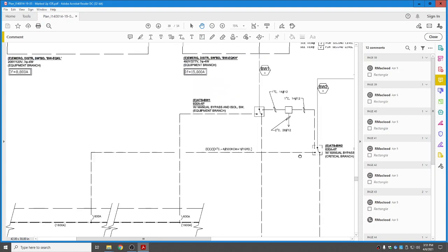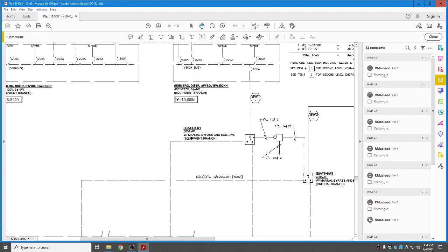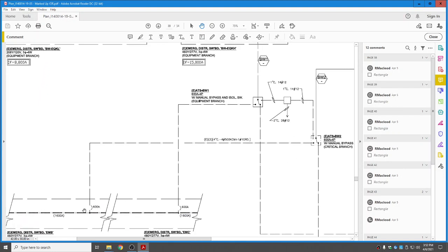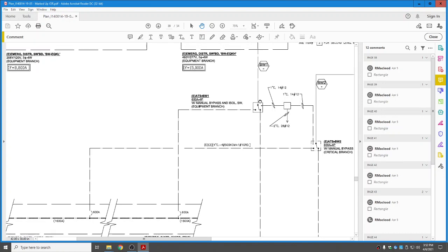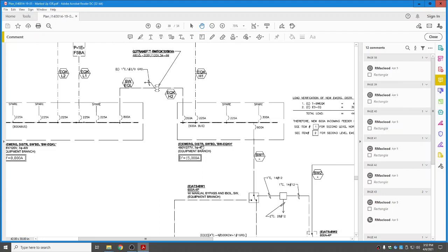Okay, now let's continue up here. You can see here we have what's most likely some power from the ATS critical branch coming up over to the equipment branch. So you can see we've got power coming from down here on the bottom. This is going to critical branch, and this 600 amp is going up to the equipment branch. From the equipment branch, we're going to be feeding emergency distribution switchboard BWEQ for equipment branch KH. That's going to be 480-277, 3-phase 4-wire equipment branch.